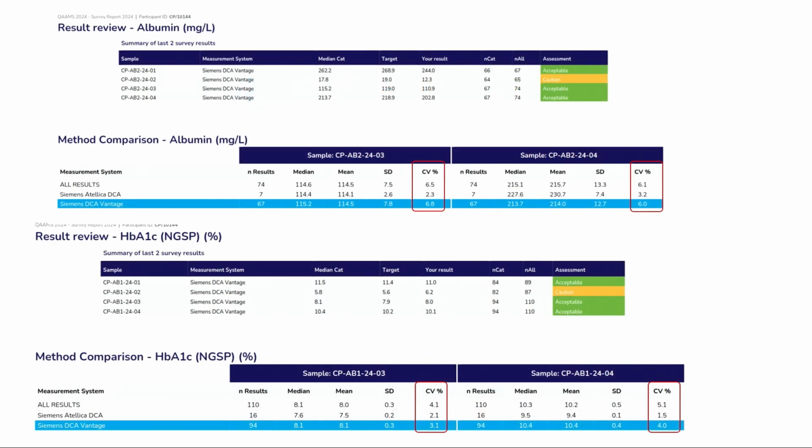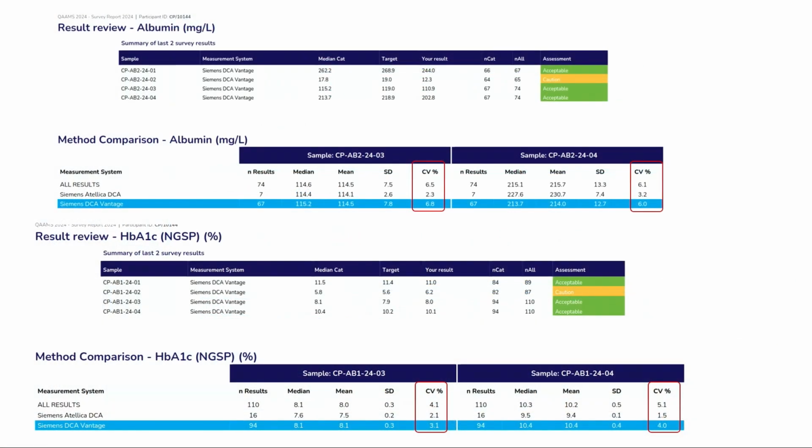This is just showing some other sort of similar results. I think Peter talked about these before. You can look at things like this for urinary albumin using point-of-care devices, and you can see that if you look at some methods, the CV is really quite low for the individual method, but CVs across all methods is high, and that's because there's bias between the methods.